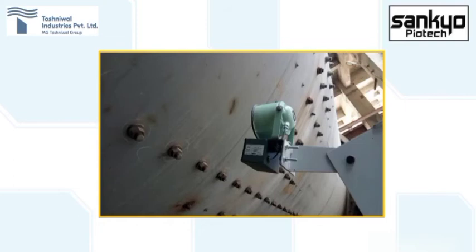The microphone is installed near the surface of the mill at a location where balls hit after lifting up in the mill, and creates structure-borne sound, at a distance of less than or equal to 200 millimeters for better sound reception.